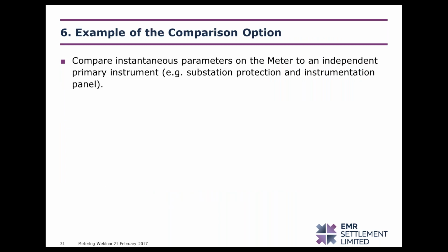If I take the example of one of these techniques and we were to compare against an independent metering system, the key consideration here is that the metering system used by way of comparison to the CMU metering must be independent, and you must be able to prove so. So a typical example would be an electrical schematic diagram submitted showing the independent metering system is connected to a different set of measurement transformers.